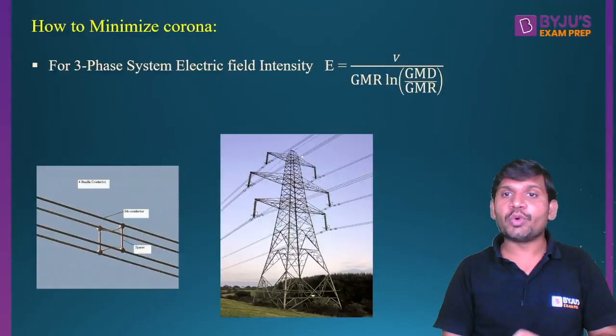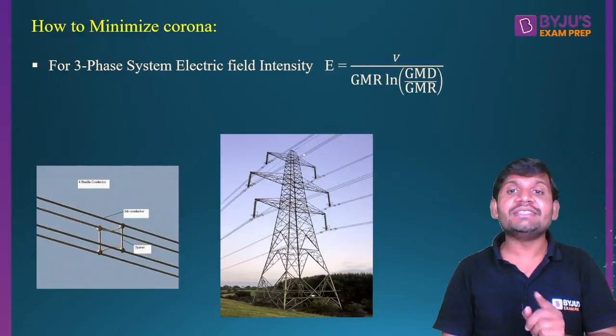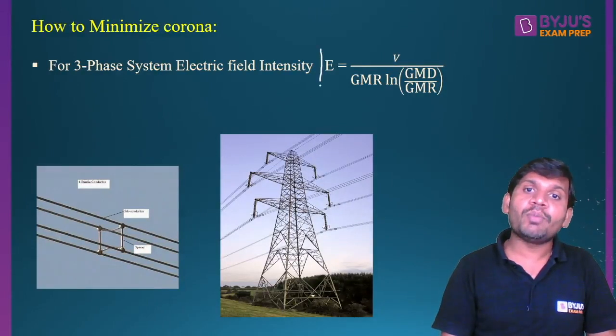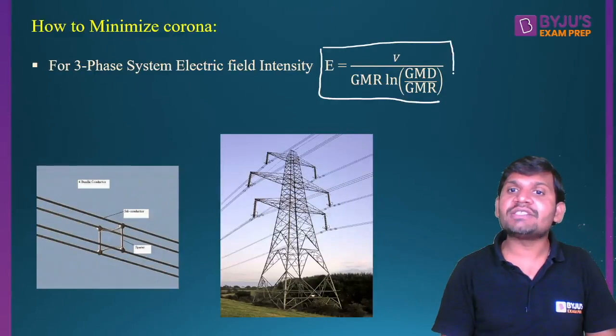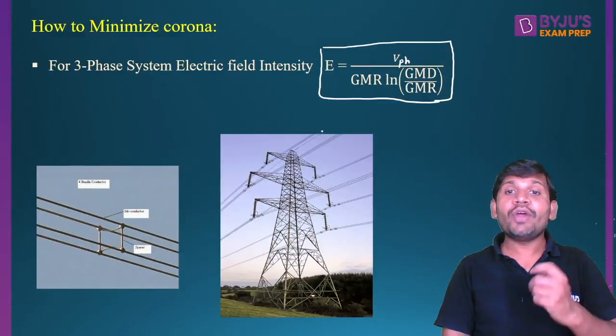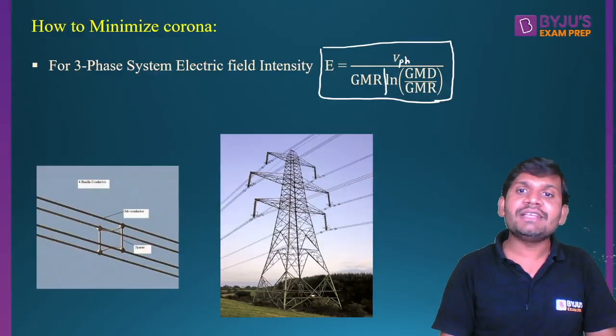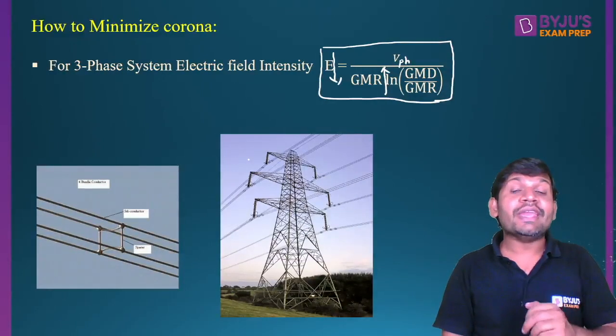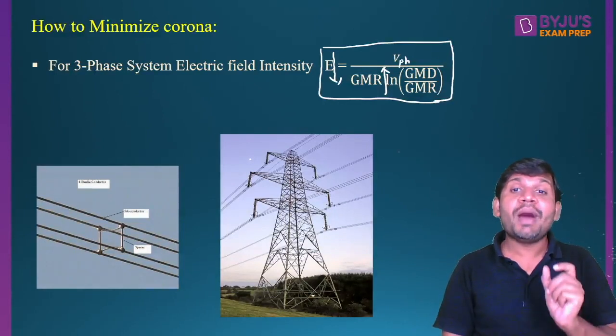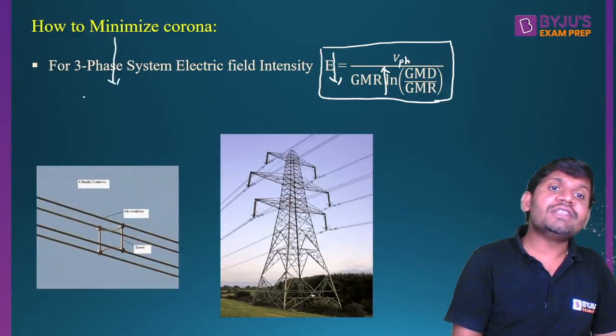How to minimize this corona effect? The main reason for corona is the large electric field intensity on the surface of the conductor. This is the formula for electric field intensity on the surface of the conductor for a three-phase system, where V is the phase voltage. To reduce the corona effect, we reduce the electric field intensity. The electric field intensity is reduced if the GMR (geometric mean radius) is increased. The GMR is increased by using bundle conductors — meaning corona is minimized using bundle conductors.